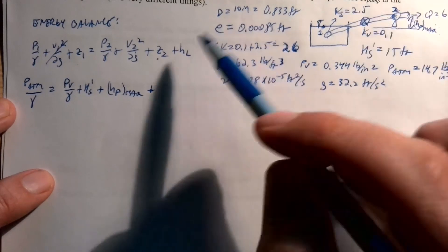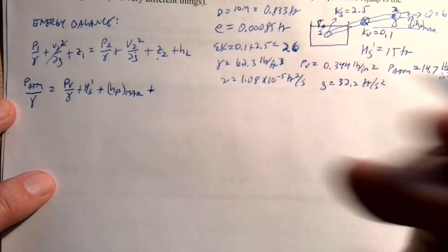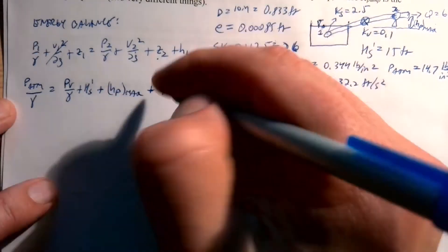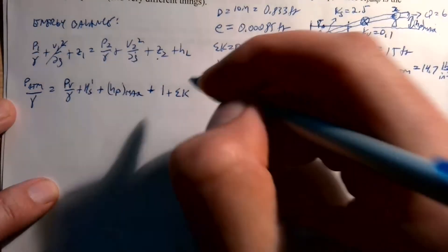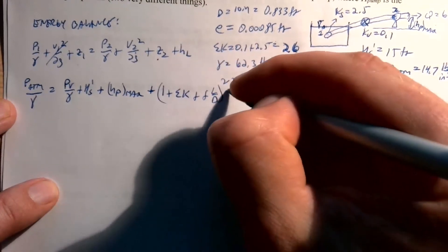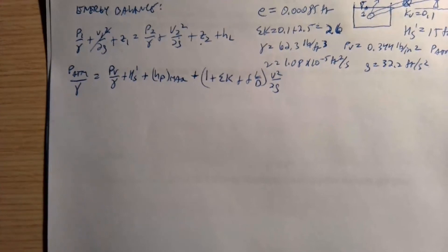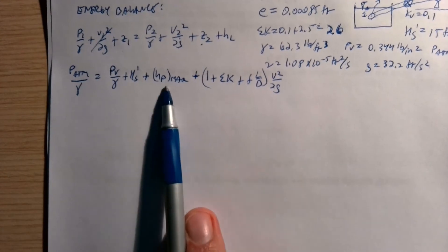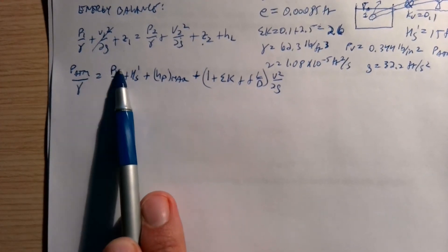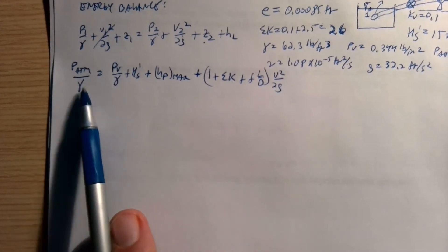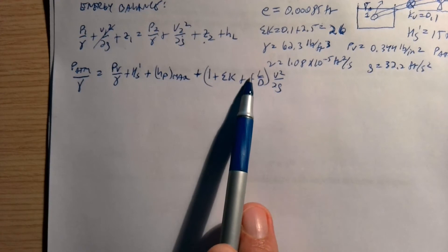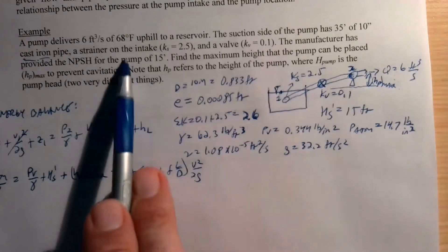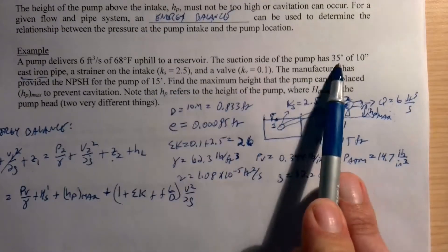There's still a velocity at point 2 entering the pump, and we have head losses including minor losses and Darcy-Weisbach friction: h_L = [ΣK + fL/D] × V²/2g. Solving for h_p max, we need: F (friction factor), V, g, L = 35 feet, D, and the given HS prime. We still need to find F, so we go get that.